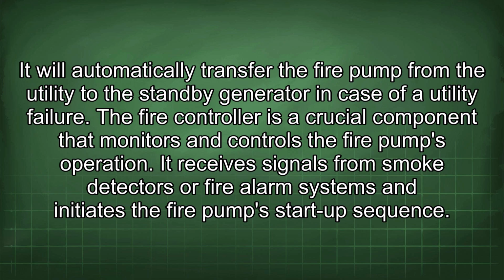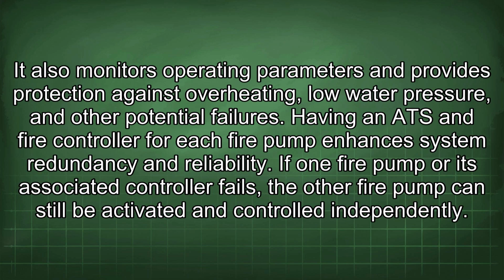The fire controller is a crucial component that monitors and controls the fire pump's operation. It receives signals from smoke detectors or fire alarm systems and initiates the fire pump startup sequence. It also monitors operating parameters and provides protection against overheating, low water pressure, and other potential failures. Having an ATS and fire controller for each fire pump enhances system redundancy and reliability. If one fire pump or its associated controller fails, the other fire pump can still be activated and controlled independently.